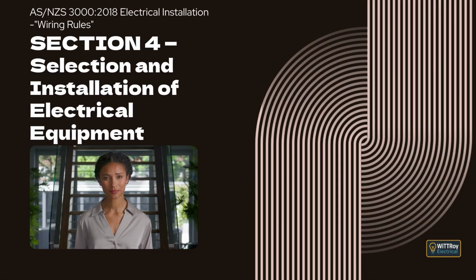Clause 4.4.4.3 Location and marking. This clause explains that the switch controlling a socket outlet must be located as close as practicable to the socket outlet and be clearly identified to show what it controls. It explains that where the switch is remote from the socket outlet, it must be installed in a convenient and accessible position, and both the switch and the socket outlet must be clearly and permanently labeled to show their relationship, with stated exceptions where the socket outlet is high above ground, dedicated to a specific appliance, and not intended for general use. Clause 4.4.4.4 Pendant type socket outlet.